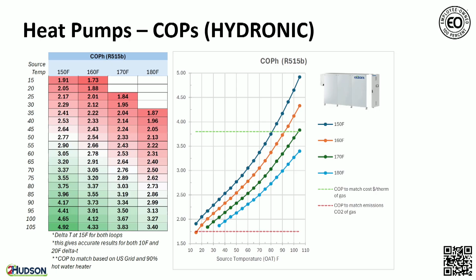To put COP charts in perspective for customers or people who do not want engineering terms, the red line on this chart is an emissions line. So anything above that, you are beating emissions of a gas or oil-fired equivalent. The green line is where you're starting to become financially efficient. So that will be local to your area. You did that green line for New York City. Electricity is not cheap in New York. So even with high COPs, in order to be financially equivalent on your utility bill, you do have to hit a pretty high mark.